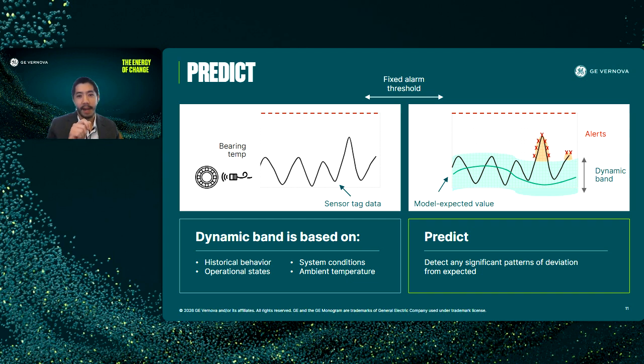I want to highlight ambient temperature—this is critical in LNG environments, where cryogenic conditions can affect things like seals and bearing lubrication. So what this means in practice is SmartSignal knows the difference between a bearing temperature that's simply elevated because of ambient temperature versus one that's high because actual degradation is occurring. Fixed alarm thresholds cannot make that distinction.